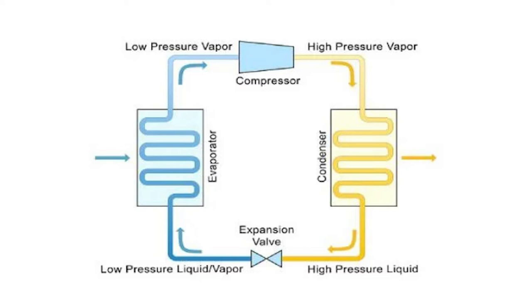The compressor pumps high pressure, high temperature refrigerant vapor into the condenser, where it is expelled to the surrounding air, thereby changing the refrigerant from a vapor to liquid state. That change of state is caused by the refrigerant temperature dropping below its vapor saturation point, which is defined as the temperature at which the refrigerant will change from a vapor to a liquid. The heat that has been expelled changes the state of the refrigerant without changing its temperature, and this heat is known as the latent heat of condensation.